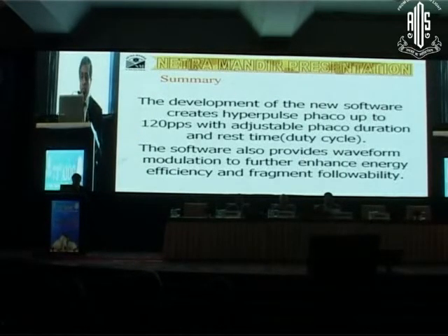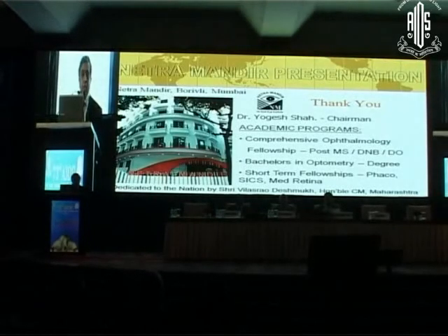To summarize, the development of the new software creates hyperpulse phaco up to 120 pulses per second with adjustment of the phaco duration and the rest time, that is the duty cycle. The software programs also provide you waveform modulation to further enhance the energy efficiency and fragment followability without generating heat and complicating the cornea.